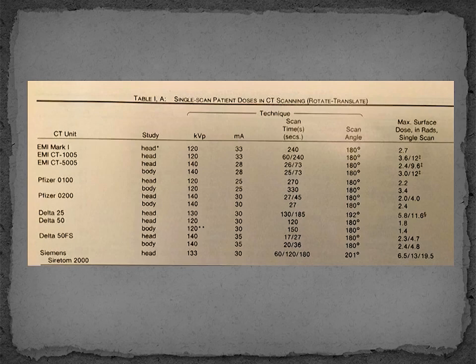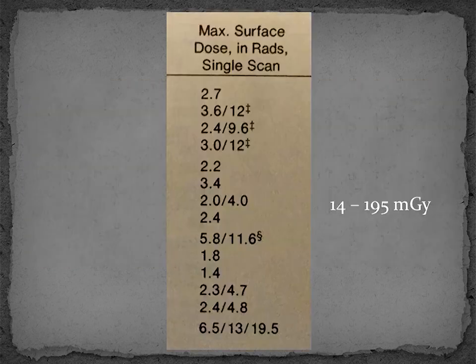While these values are hard to read, they demonstrate that measurements were made over many different scanner types and scan parameters. These doses are in rads, so I've converted the values into milligray as is commonly used today. These values are the peak dose from one scan, and in some cases the dose reached up to 200 milligray. There were many different scan options, and this led to considerable variability in the doses delivered from a single scan.